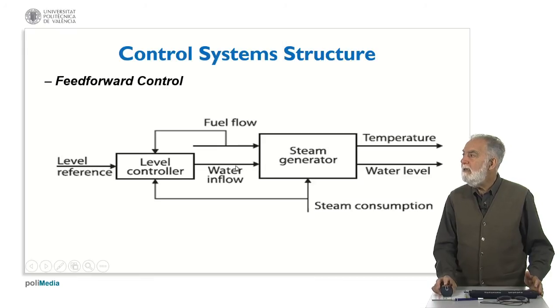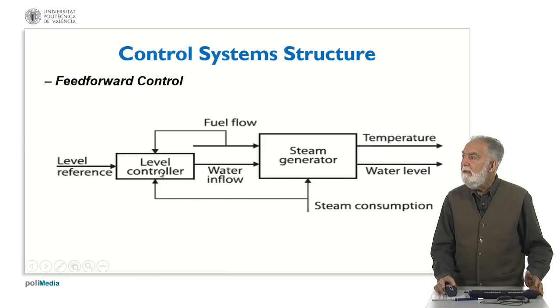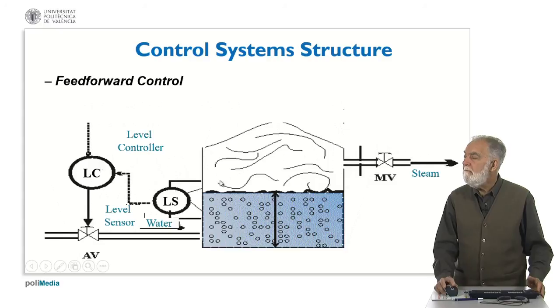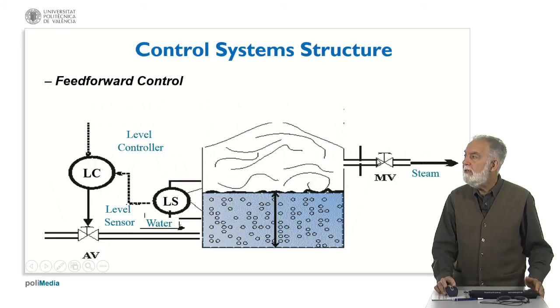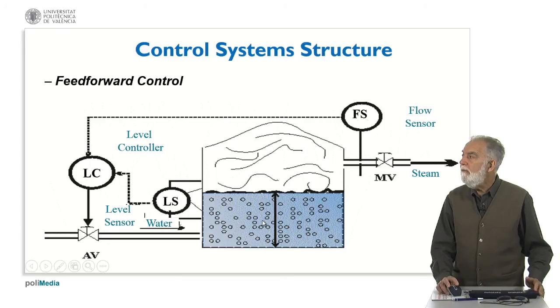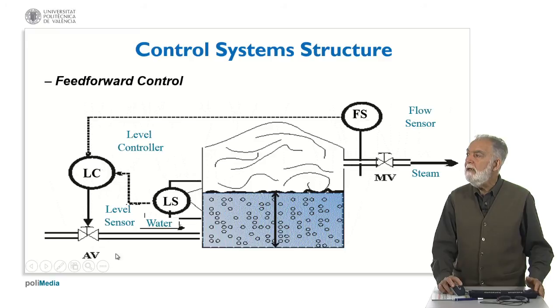You can see here an example. The level can be controlled by the level controller, but if we know that there is an extra consumption of steam, then we can modify the inflow. This is seen in the picture: more water will be drawn, and before we measure the level dropping, we can increase the water flow. So we can add a flow sensor here and generate an extra input to the controller.